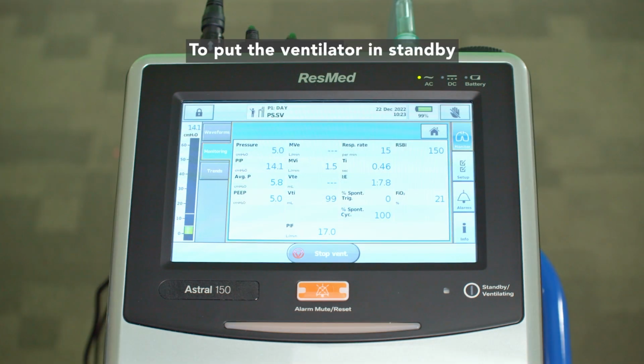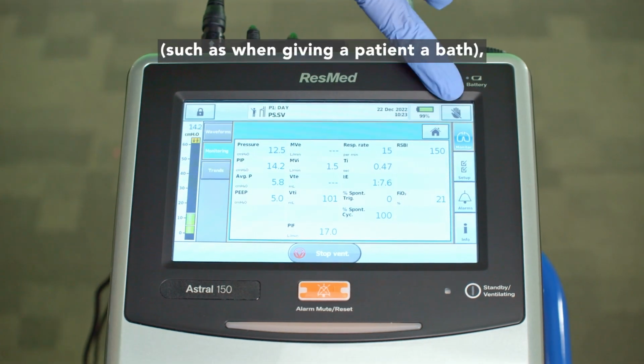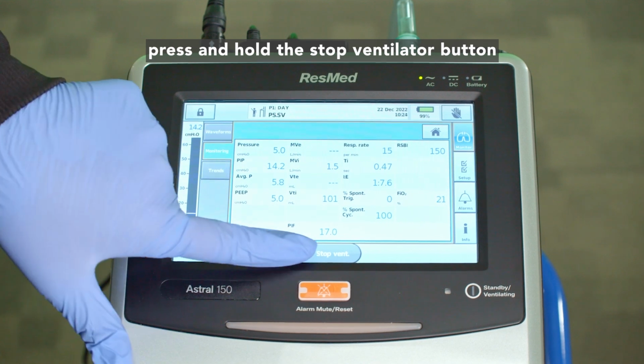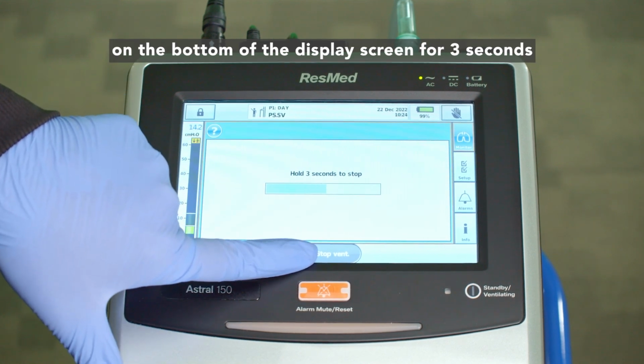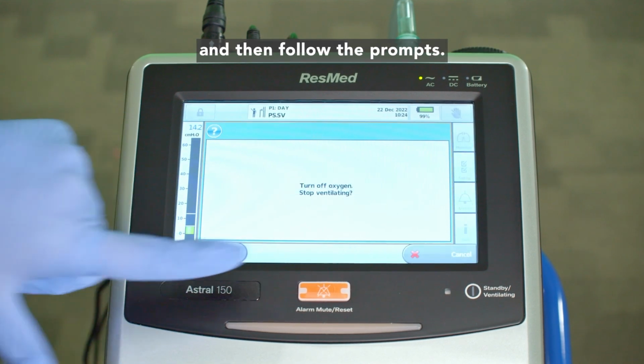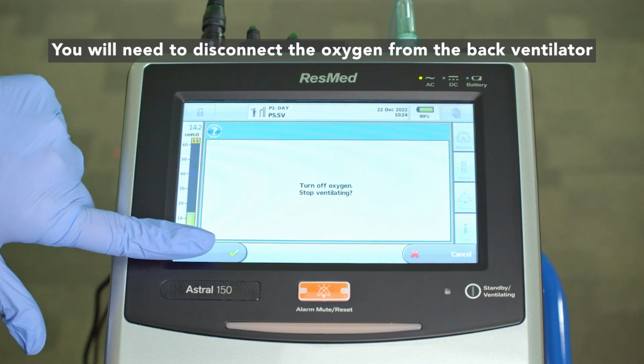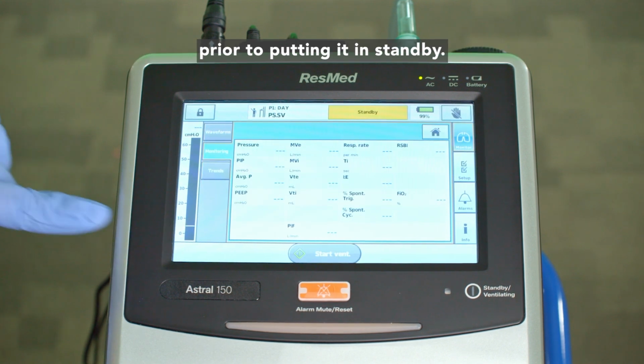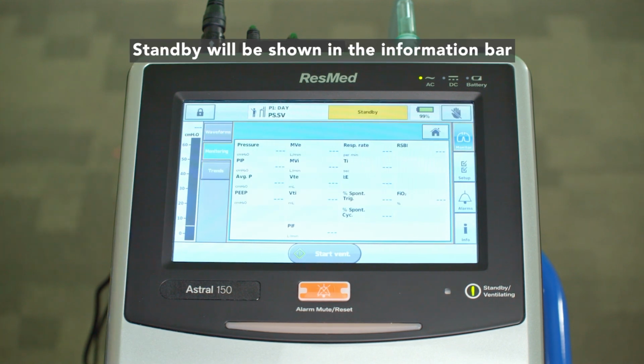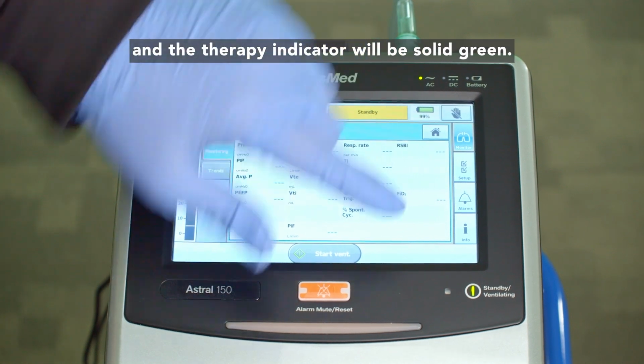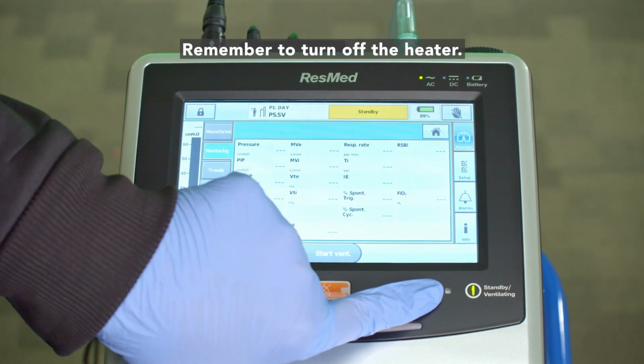To put the ventilator in standby, such as when giving a patient a bath, press and hold the Stop Ventilator button on the bottom of the display screen for 3 seconds and then follow the prompts. You will need to disconnect the oxygen from the back of the ventilator prior to putting it in standby. Standby will be shown in the information bar and the therapy indicator will be solid green. Remember to turn off the heater.